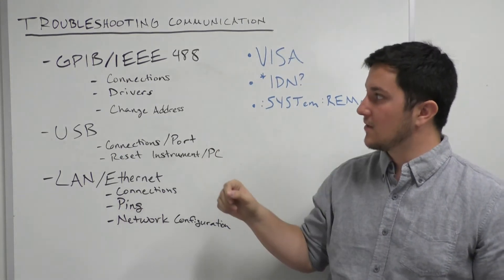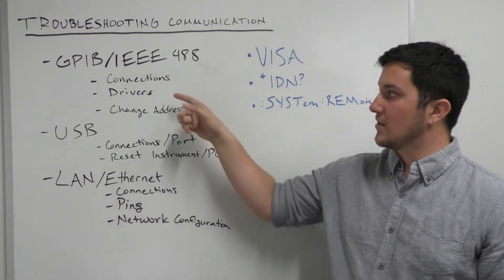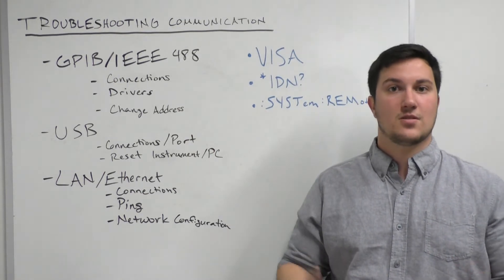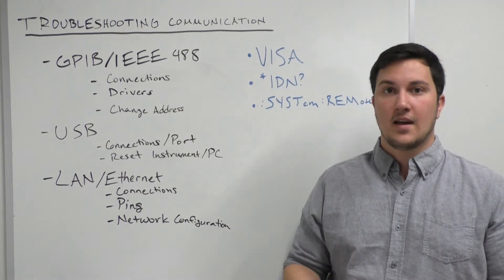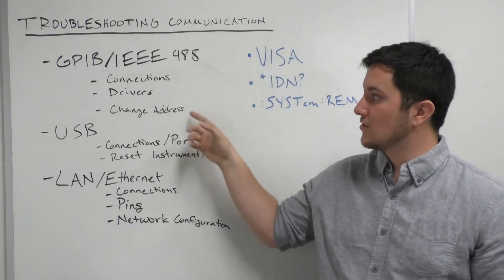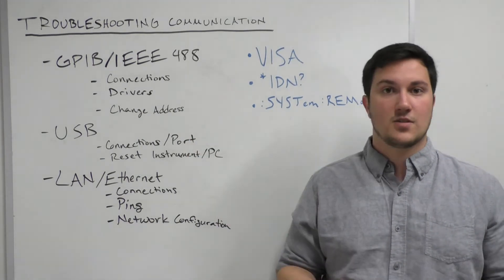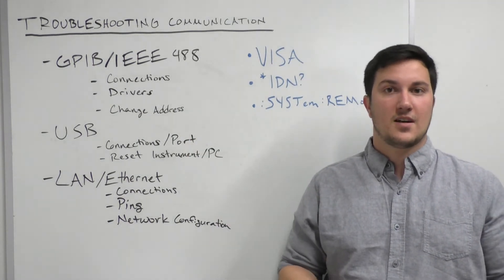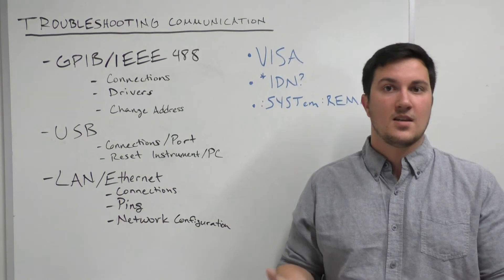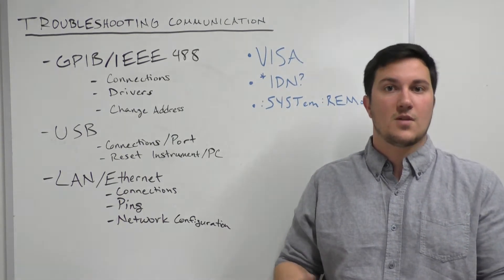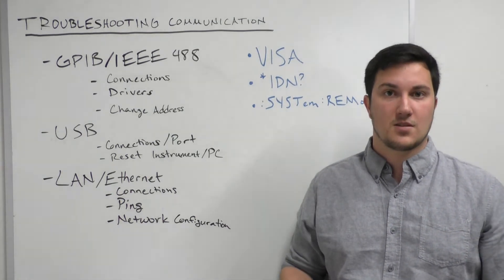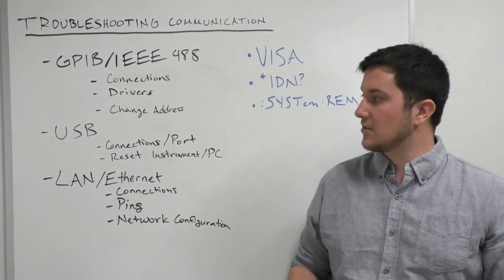For GPIB specifically, you want to make sure that any drivers for your adapters or your instruments are installed. If that doesn't fix your connection issues, you can also change your instrument address. Usually this would be if you have two instruments on the same address — it'll cause some communication issues, so you want to make sure those are different if you have multiple instruments on the same GPIB connection.